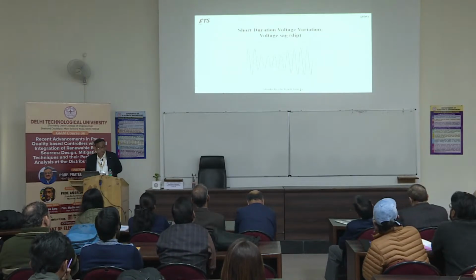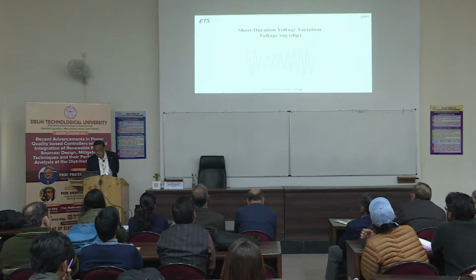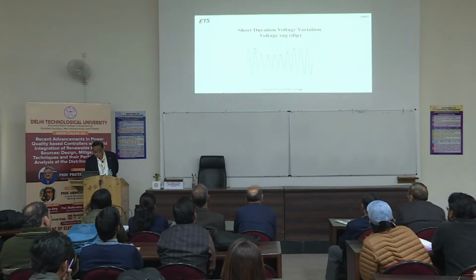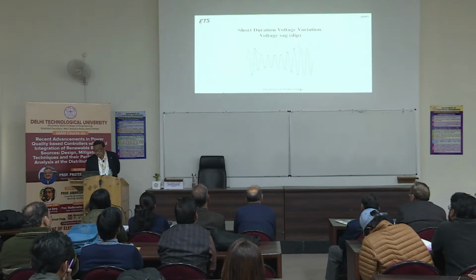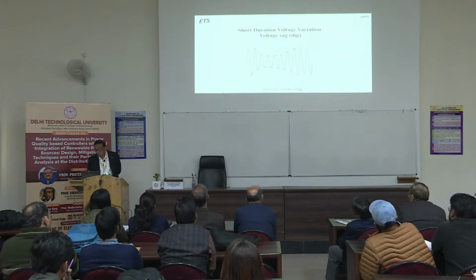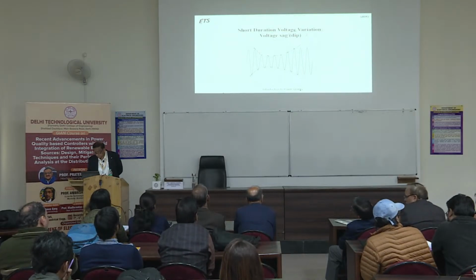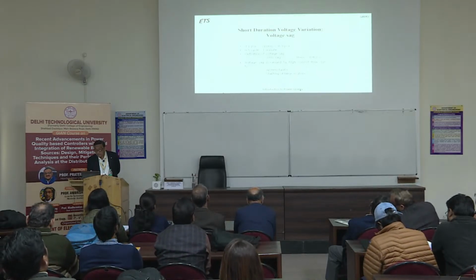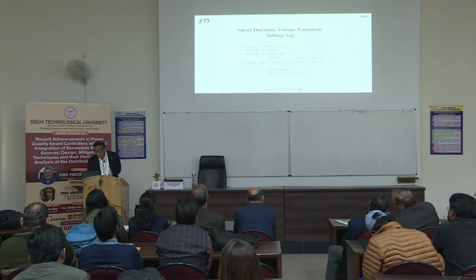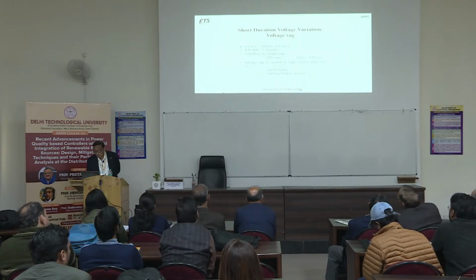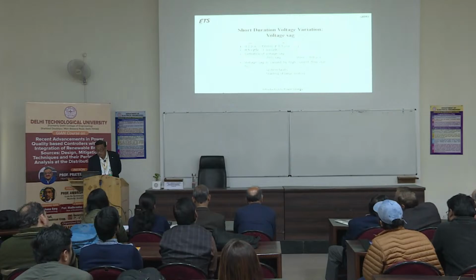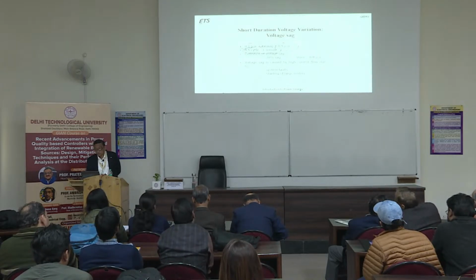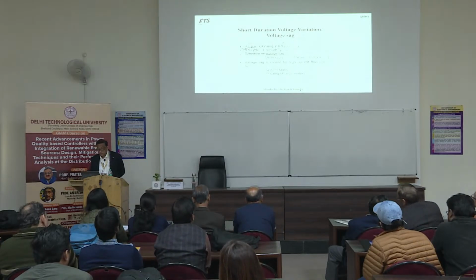Short duration voltage variation. Okay, so you can see for short duration, for few cycles, you have voltage sag. In Europe, they call it dip. So voltage sag may be between 0.1 pu to 0.9 pu, between half cycle and 1 minute. So that is short duration voltage sag. So if we say 20% sag, it means VRMS is 0.8 pu.